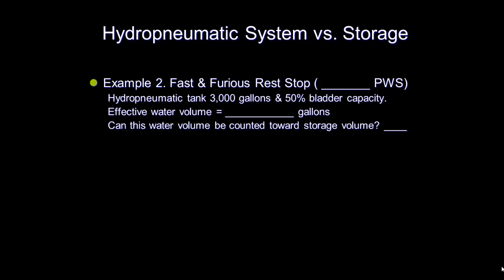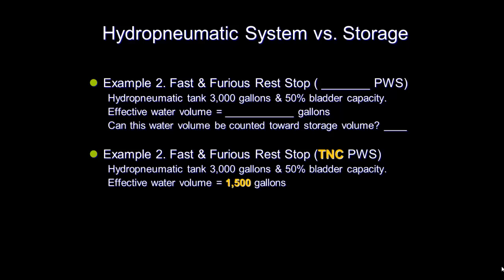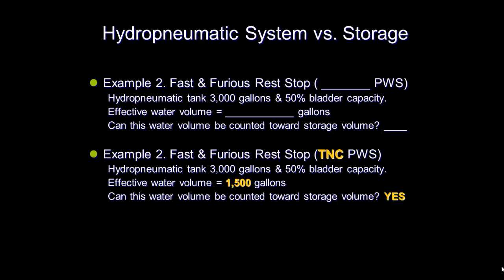Using the same scenario for the fictitious Fast and Furious Rest Stop, the following can be determined. This system is a transient non-community water system. The effective volume is the same as before at 1,500 gallons. But since this is not a community water system, the volume of the hydropneumatic tank counts towards the required storage capacity.